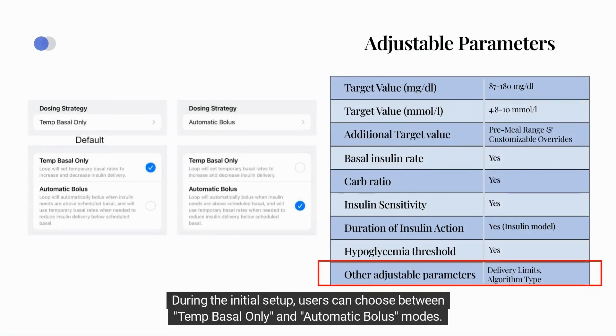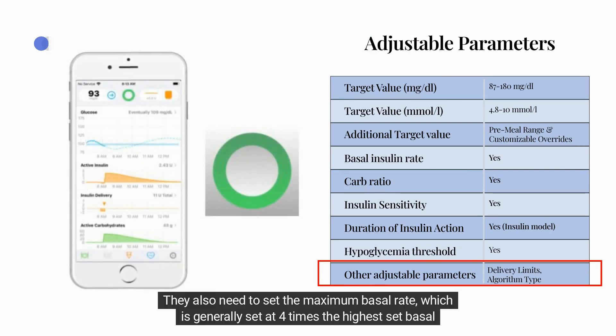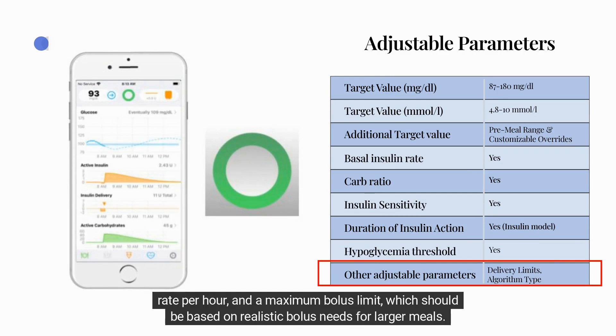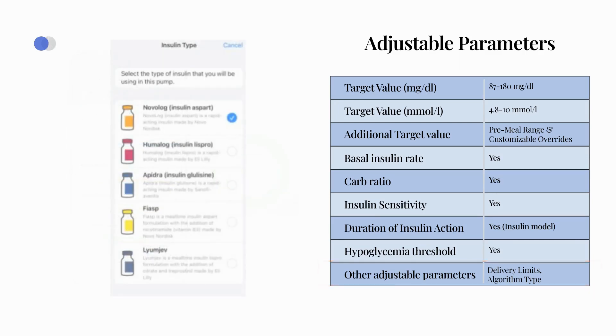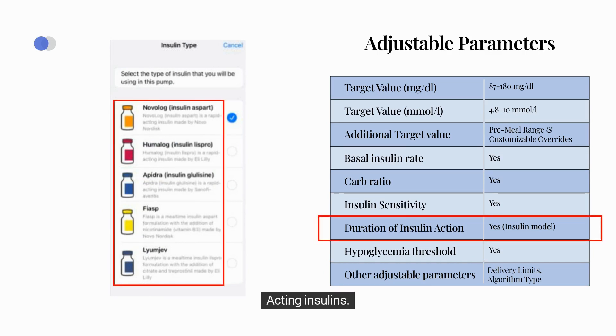During initial setup, users can choose between Temp Basal Only and Automatic Bolus modes. They also need to set the maximum basal rate, generally set at four times the highest set basal rate per hour, and a maximum bolus limit based on realistic bolus needs for larger meals. Furthermore, users have the option to choose an insulin model tailored for rapid-acting or ultra-rapid-acting insulins.